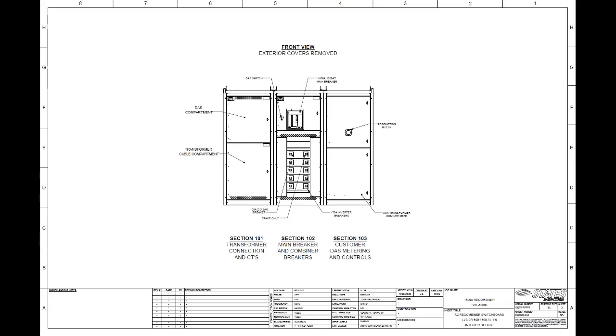Once we get to the inside of it, this is where states can really shine in our customization for what the engineer, what the developer wants for a layout. In this case, they were requesting that the group mounted breakers be directly tied into the main disconnect, and then that feed over to different metering compartments. So we're able to stack a main breaker in a 1600 amp up to 2000 amps directly above the required number of inverter breakers where they're doing the paralleling.